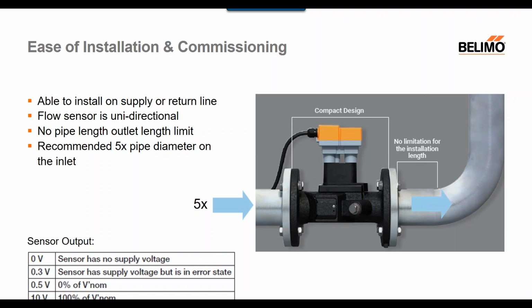Ease of installation and commissioning. Belimo flow sensors can be installed on the supply or return side of the system, and the focus is on easy installation features such as a low profile compact design for tight spaces. There is also no pipe length limit for the outlet installation side. And on the inlet, we recommend that there is 5 times pipe diameter limit to maintain true accuracy. Flow sensors are unidirectional, and if installed backwards, or if there are air bubbles present, the Belimo flow sensor will show error state output of 0.3 volts, enabling effective and sure troubleshooting.